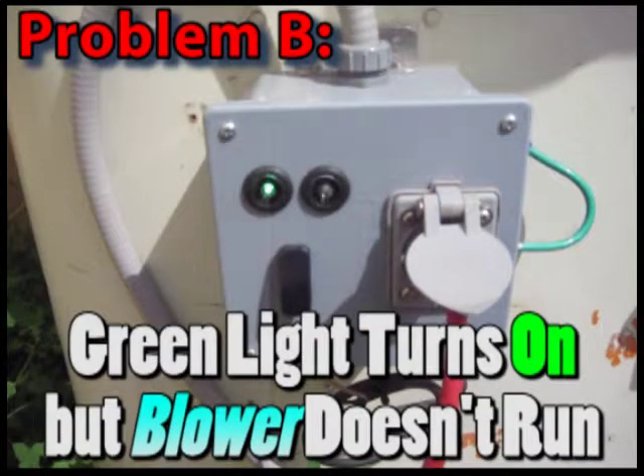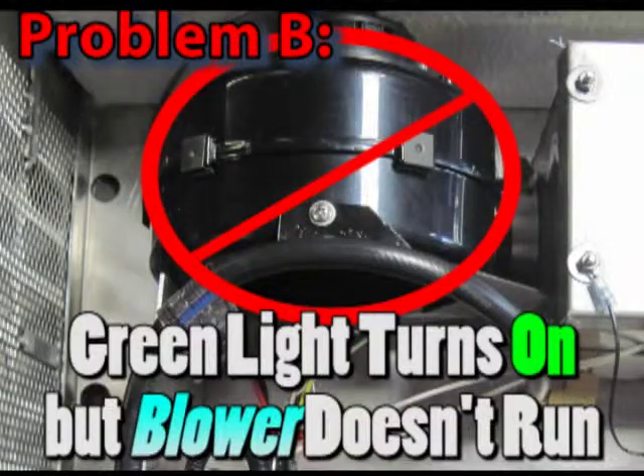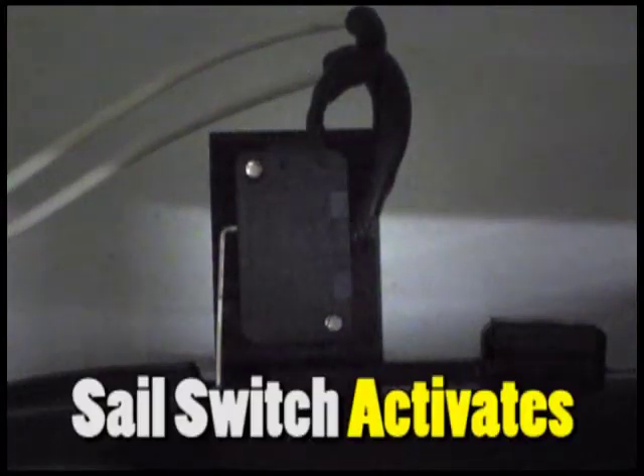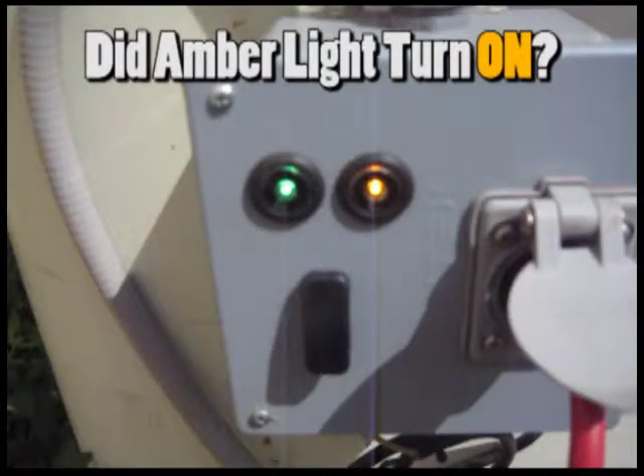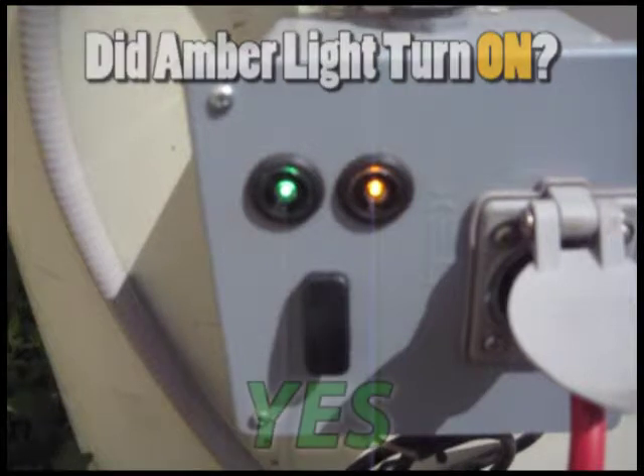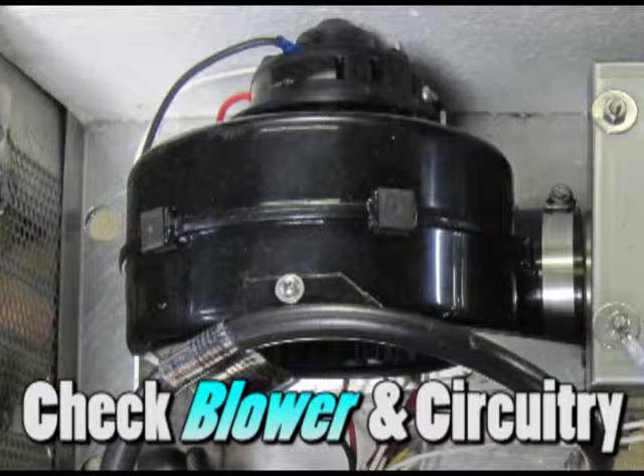Problem B. The green indicator light comes on, but the blower does not run. Attempt to mimic blower operation by pressing on the activation lever of the sail switch mounted on the blower. Does the amber indicator light on the control box turn on, indicating the start of the ignition phase? If so, focus troubleshooting on the blower and the associated circuitry by checking the following list of items.